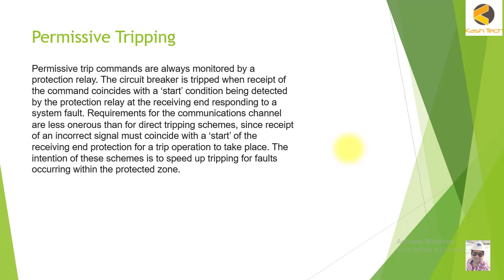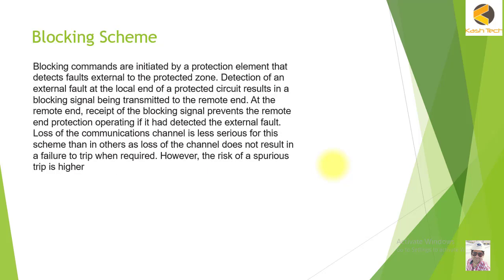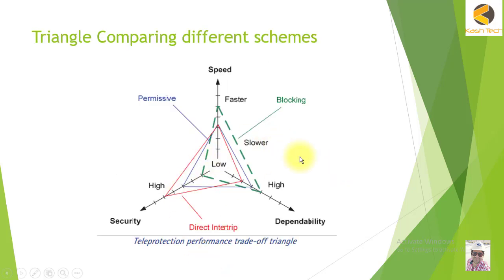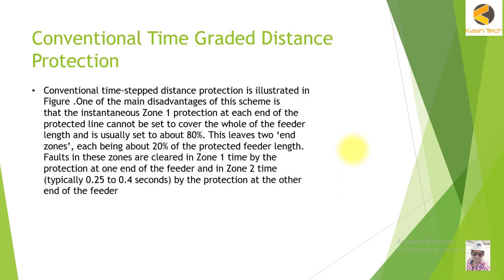With permissive tripping, a trip signal is sent to the other end, but the remote end checks additional conditions before allowing tripping — otherwise it does not trip. We will also study the blocking scheme, and then we will look at the advantages and disadvantages of various teleprotection schemes. Some schemes are faster, some are slower, some require high security, and some have low security.